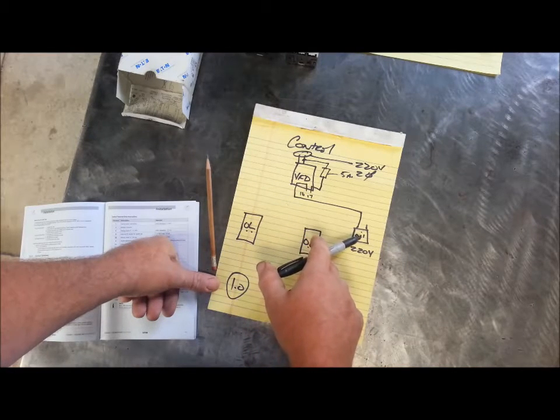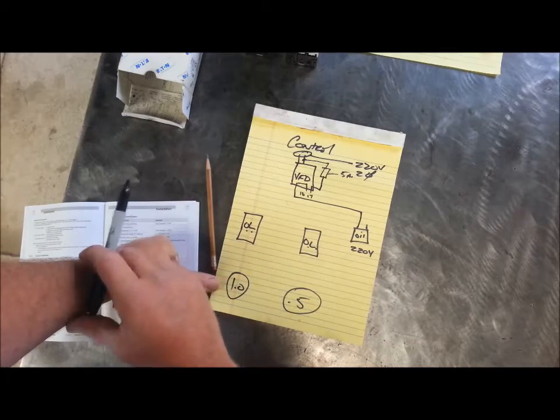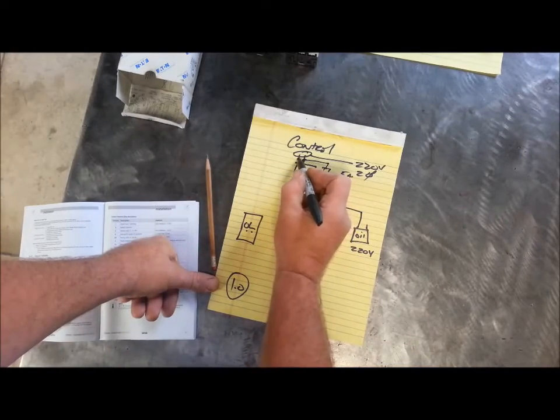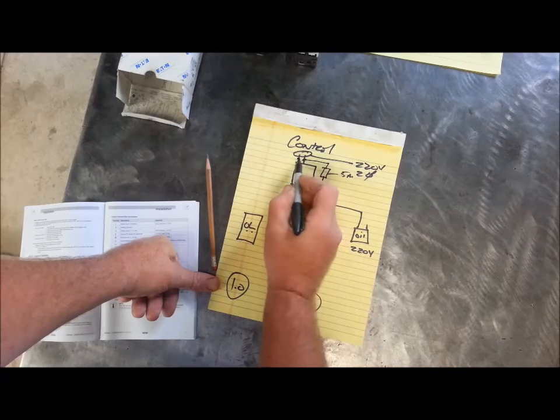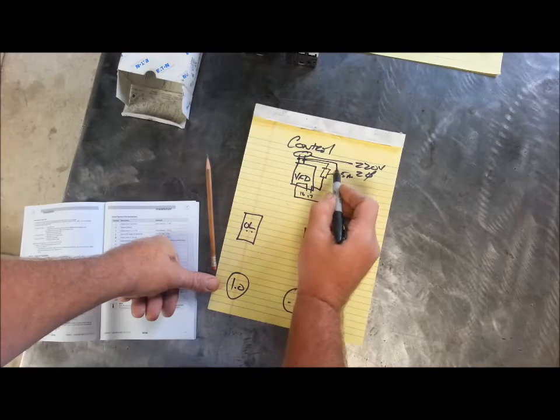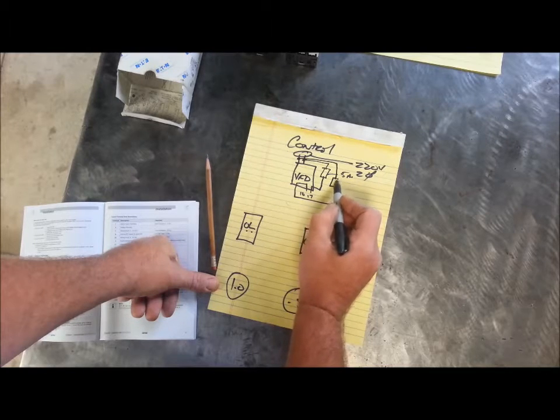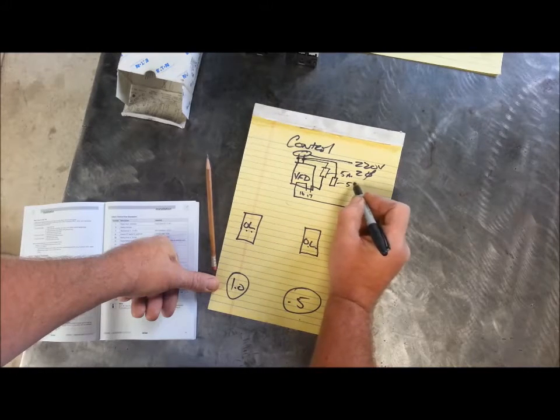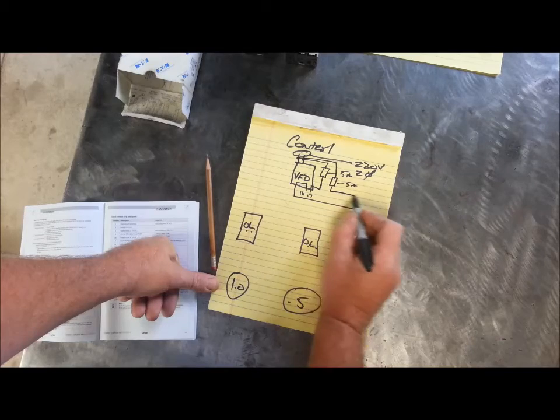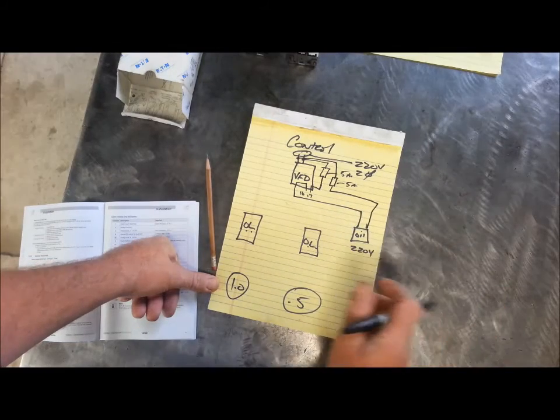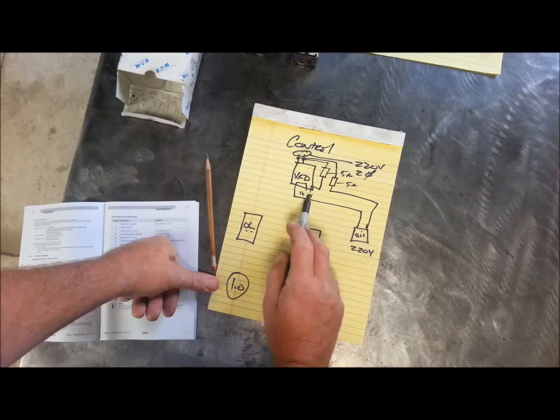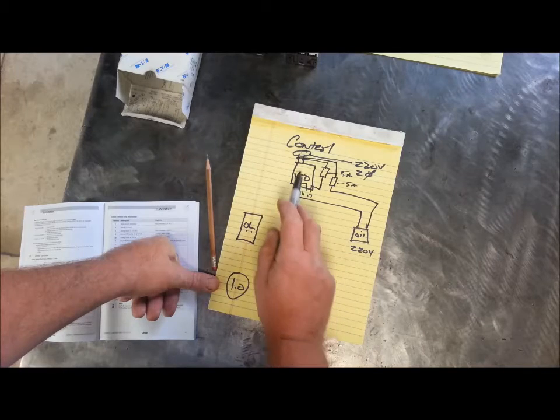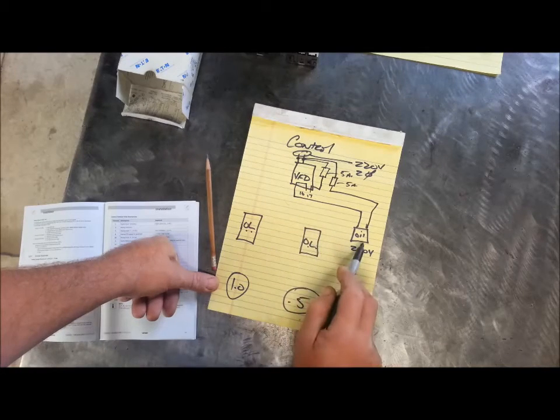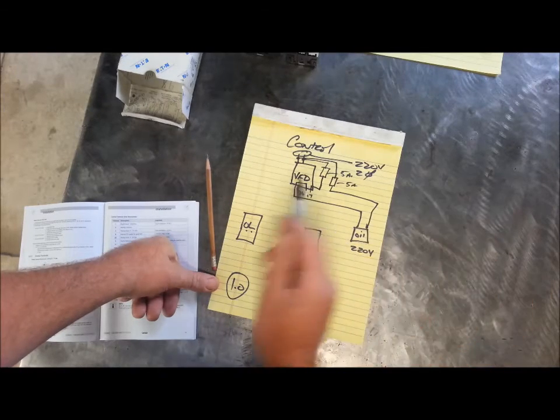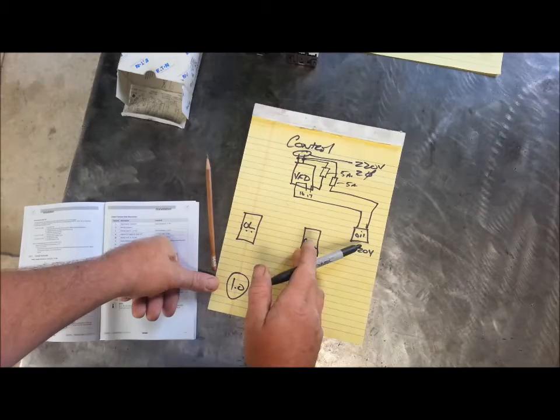The oiler is intended to run whenever the main spindle is running. Off the other line, we need to power up this other terminal, and that can just go direct. So you'd come out here, do a second fuse, also 5 amp, and power up your oiler. So now when 16 and 17, when that switch closes, when the VFD is given a run command, our oiler is running. All right, so that takes care of our oiler and that switchgear.